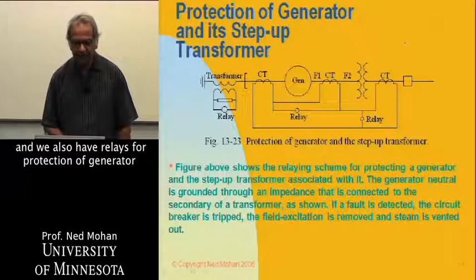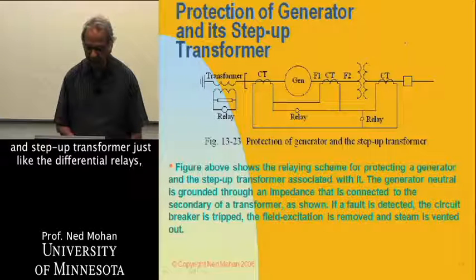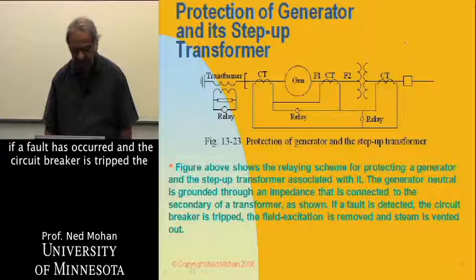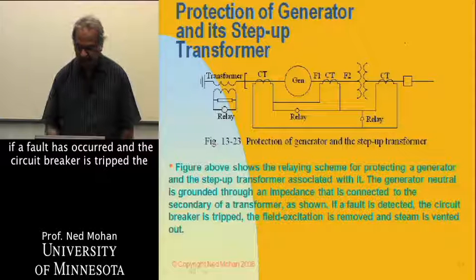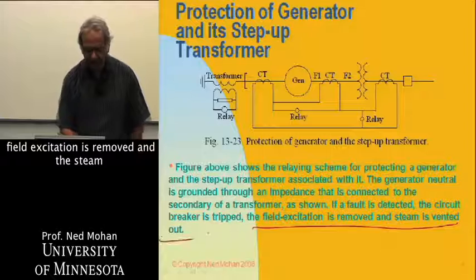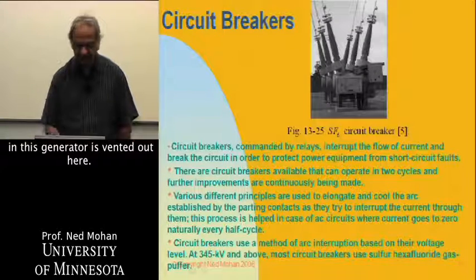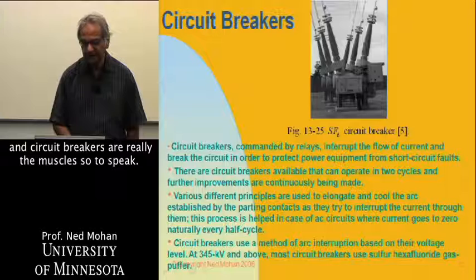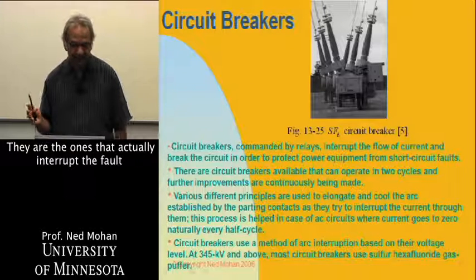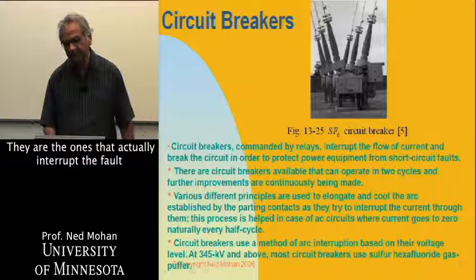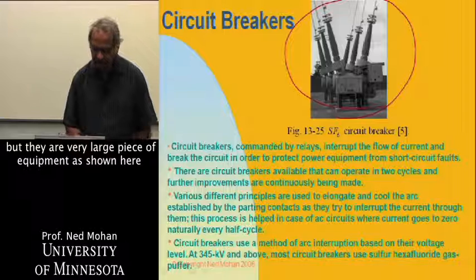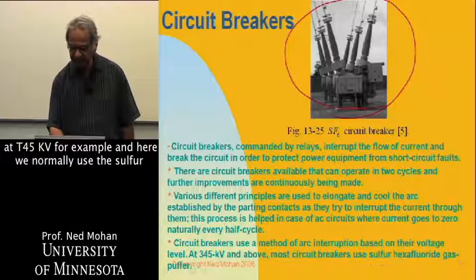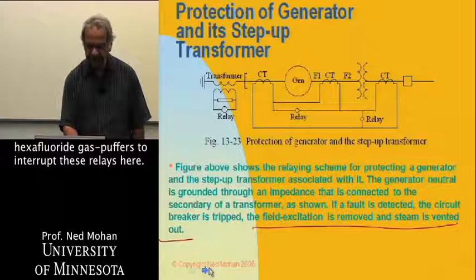We also have relays for protection of generators and step-up transformers, just like differential relays. These can determine if a fault has occurred, the circuit breaker is tripped, the field excitation is removed, and the steam in the generator is vented out. Then we have circuit breakers — the relays are the intelligence, and circuit breakers are the muscles. They are the ones that actually interrupt the fault. They are very large pieces of equipment, as shown here at 345 kV, and normally use sulfur hexafluoride gas puffers to interrupt the current.